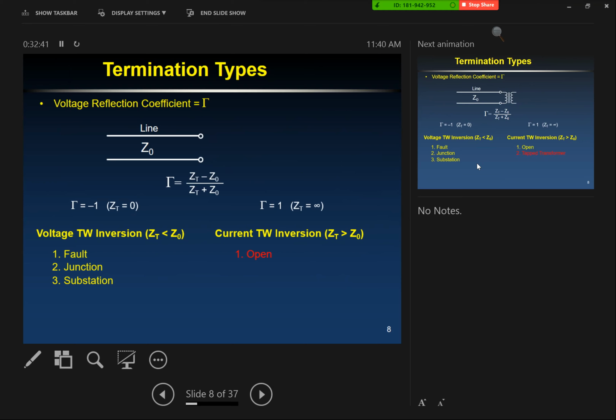So we'll see that. Let's say we energize a line. Your end is open because the line was de-energized to start with. You energize the line, you'd expect to see perfect current inversion off the end of that line coming back at you. And we would do that when we're first trying to find the propagation delay of a line. You energize the line, you do that test, you actually see that bounce of the current off of the end of the line and come back. And then knowing that difference in time, you can calculate your propagation delay.